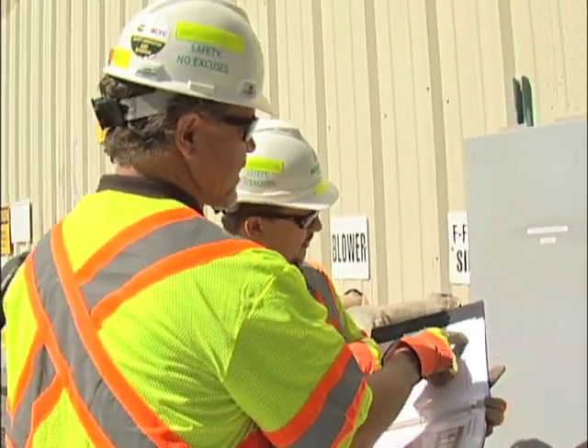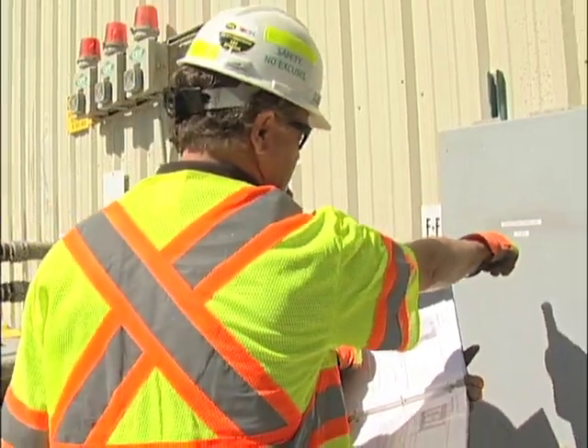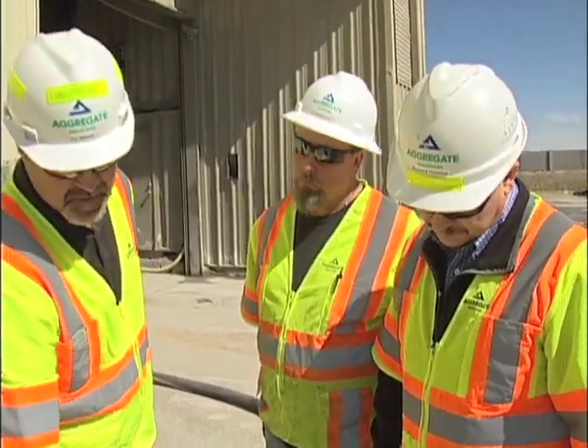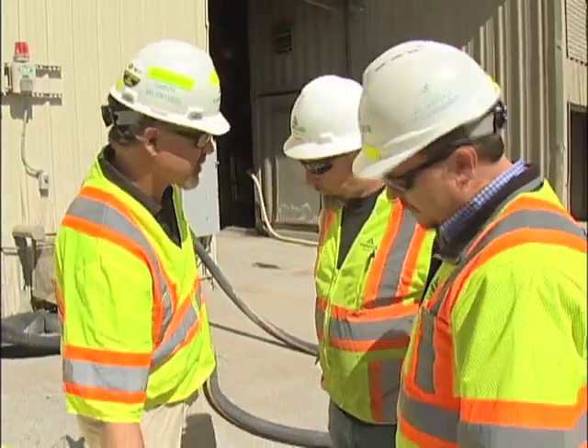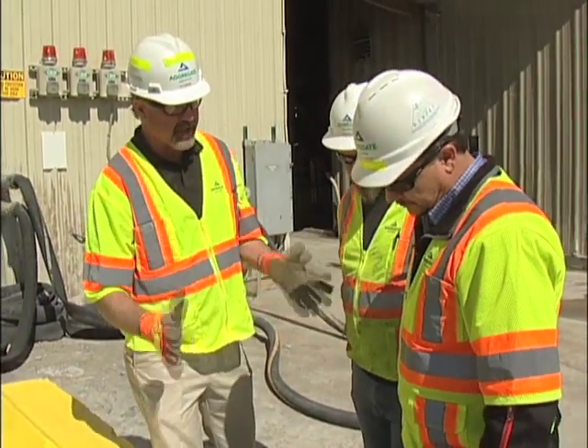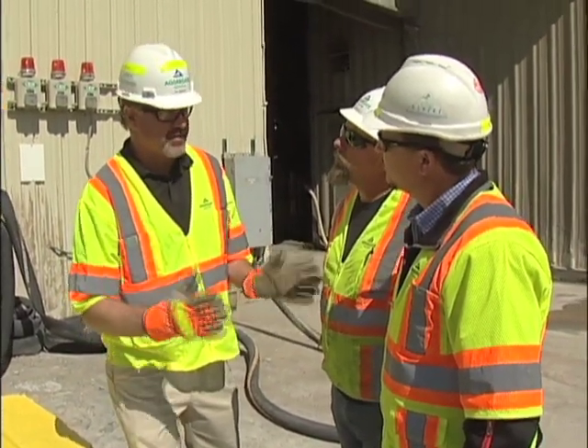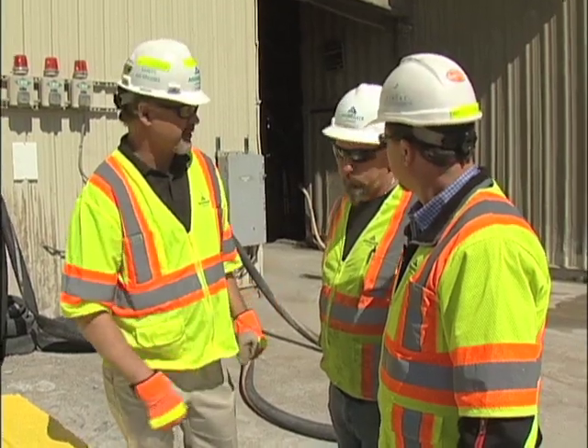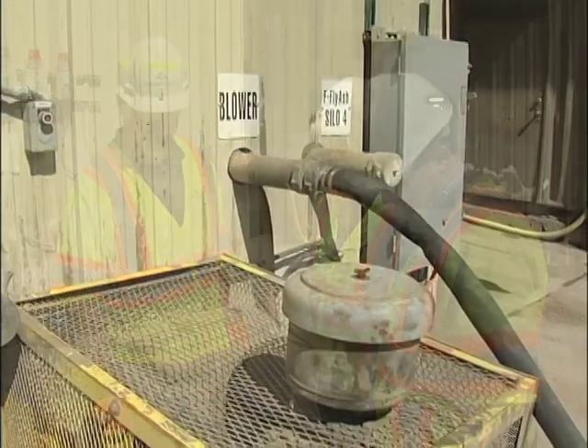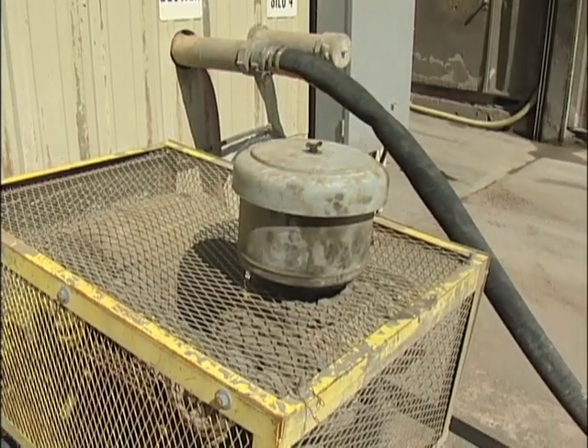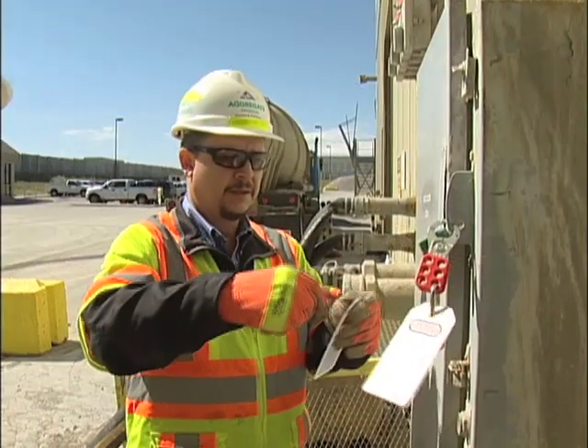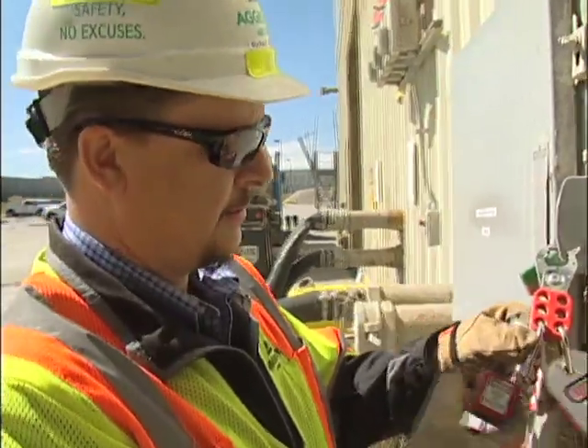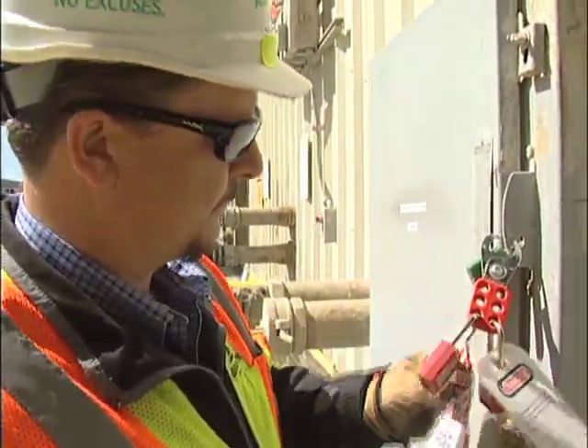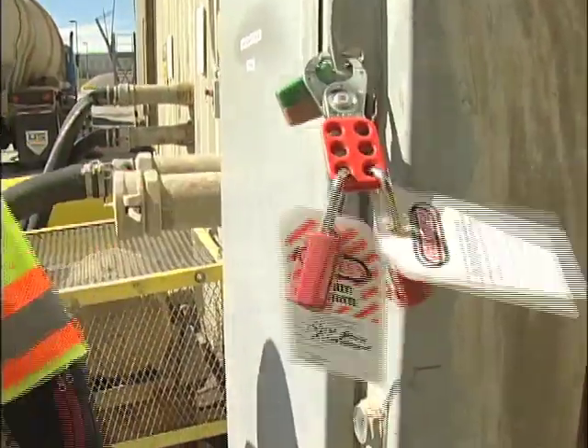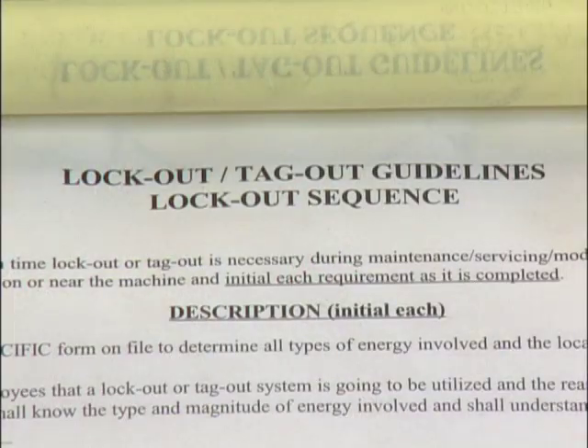Also, don't just assume that because you performed this task many times before, that by memory alone, you know all of the important energy control procedures. Existing equipment may have been replaced or repaired, or new equipment may have been modified requiring new lockout, tagout, and tryout procedures. Additionally, as a best management practice, use a lockout, tagout, and tryout logbook each time a device is applied to the equipment and is then removed.